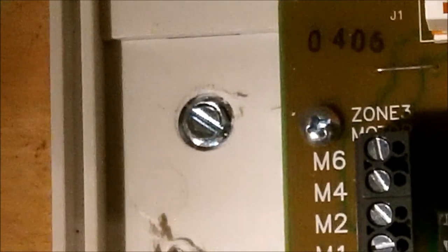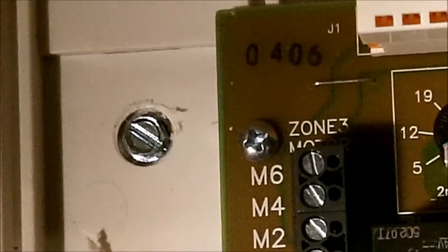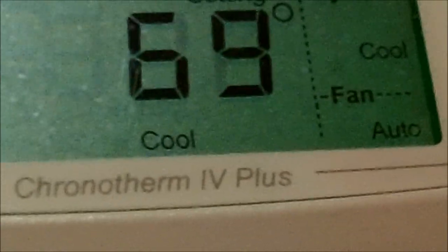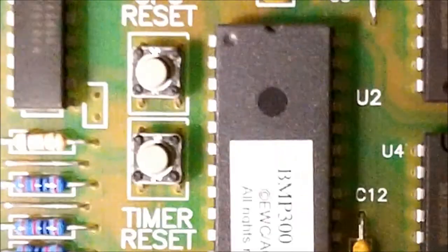I'll show you, I've got some ice out here I can put on the outdoor sensor, so when it cools down you'll see what happens there. So while we're doing that, let's go ahead and switch it over to cooling. Alright, so that one's on cooling. Switch zone 2 on cool. Right now it's on cooling. We'll run it down. 61 should be fine. We'll do the same thing on this one here. 61. Okay, this board has a 3-minute time delay.